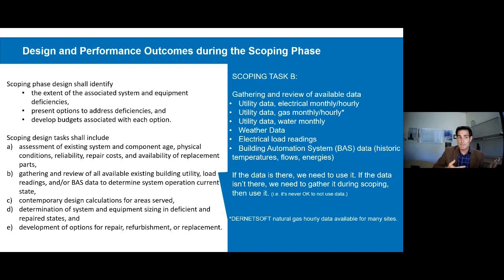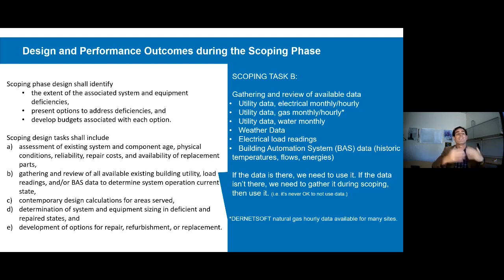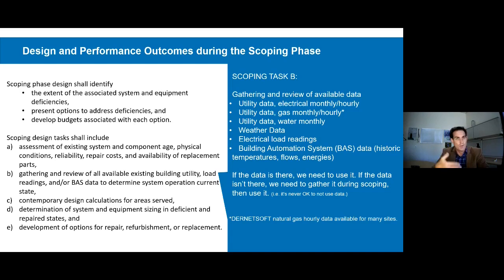We also have 15-minute interval data available — we have to request it, but we always can. We always have weather data available; if the building has an automation system we can pull weather data from that, but even without one there are free, readily available websites where you can pull last year's historical weather data for really anywhere in the world. For electrical projects we require load readings as part of the project.